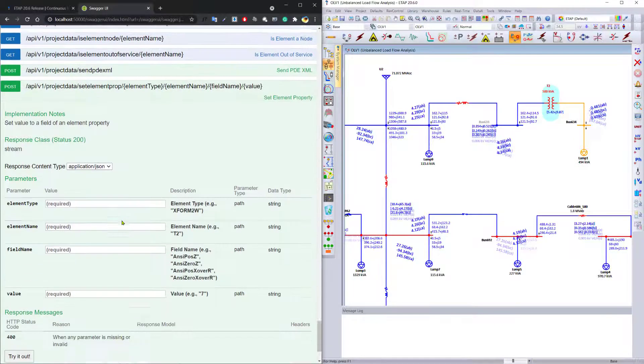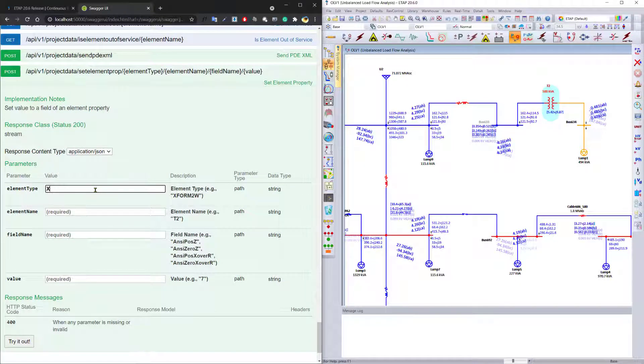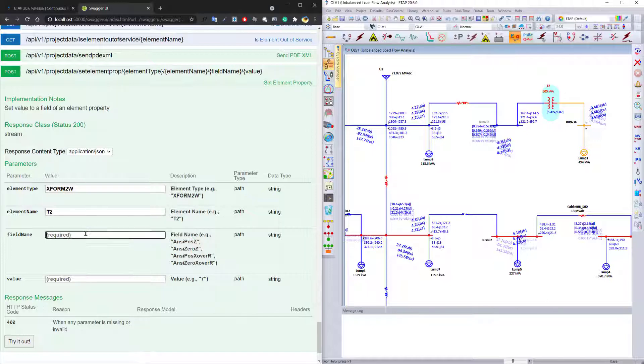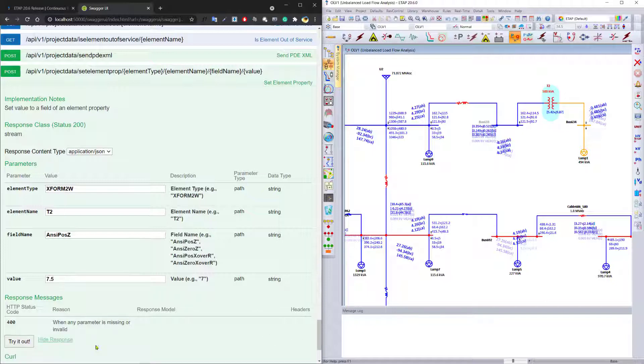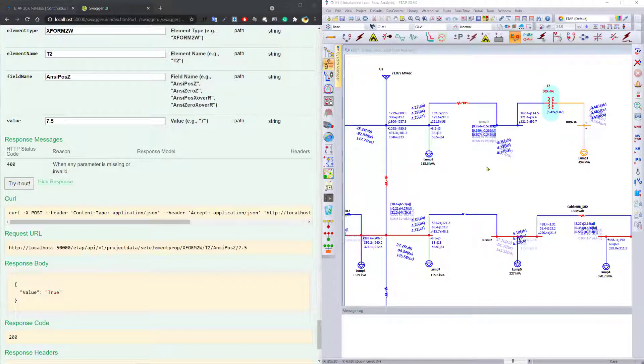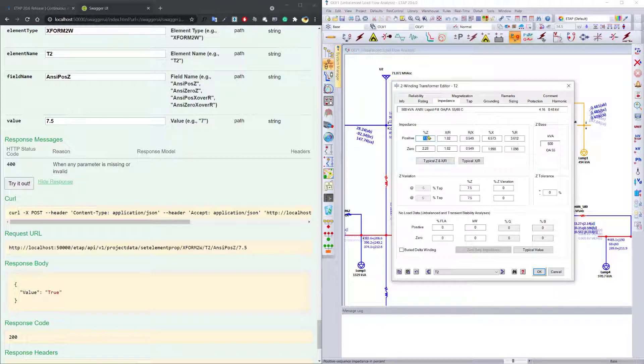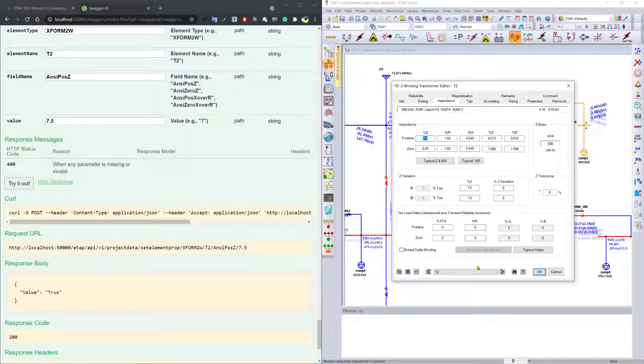You can also use the same tool to set the value of the property for this element. We set the value for the ANSI positive sequence impedance, and the value you would like to set to is 7.5, and we can go ahead and apply it, and then open up the program to make sure that it actually has been applied.